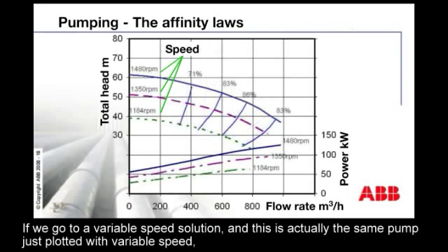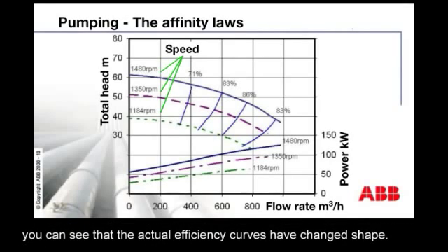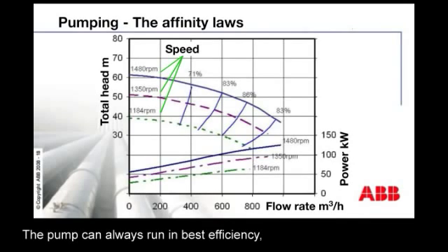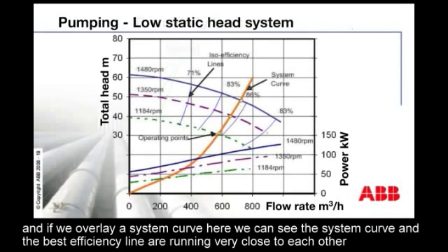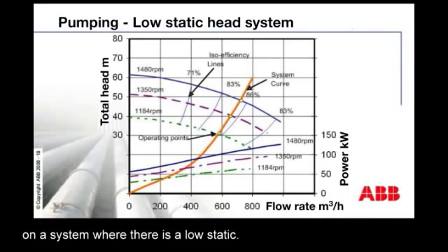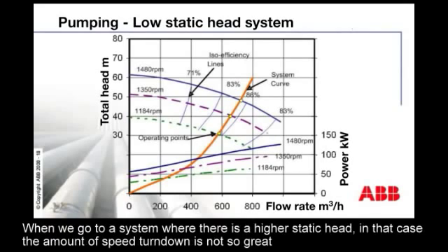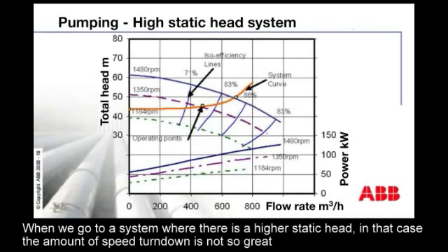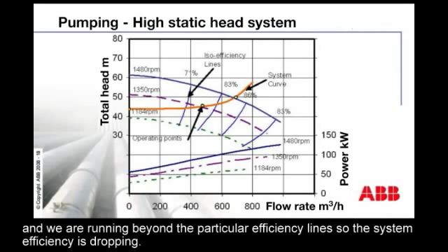If we go to a variable speed solution — and this is actually the same pump plotted with variable speed — you can see that the efficiency curves have changed shape, and the pump can always run at best efficiency. If we overlay a system curve, we can see the system curve and the best efficiency line running very close to each other on a system with a low static head. When we go to a system with a higher static head, the amount of speed turn-down is not so great, and we are running beyond the particular efficiency lines, so the system efficiency is dropping.